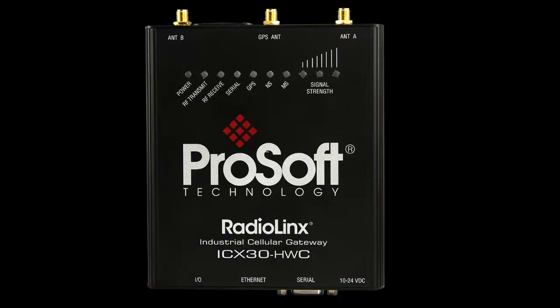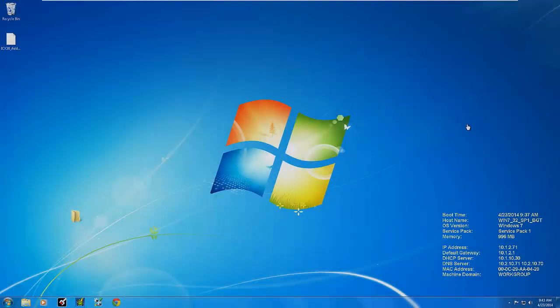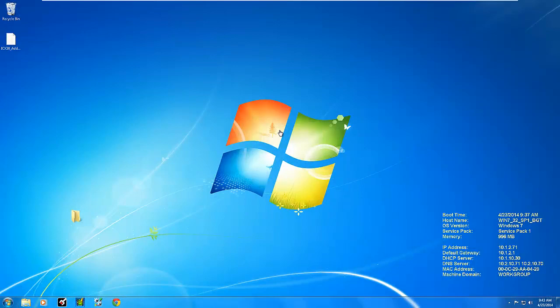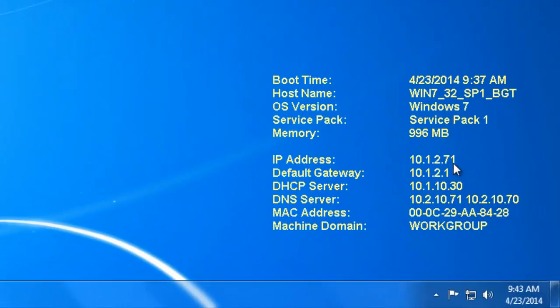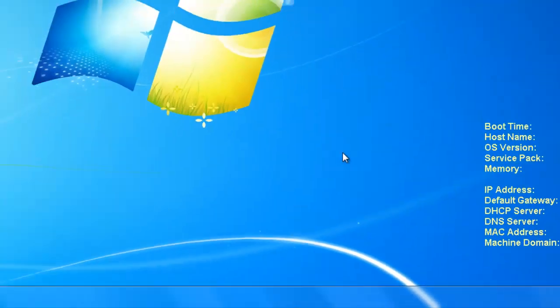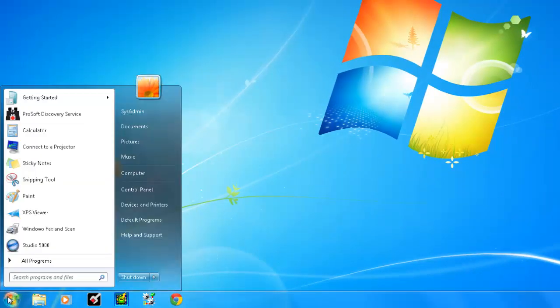When you receive your module it is set to a default IP address of 192.168.0.250. In order to configure this radio we need to have access to that web page. Instead of changing the IP address of your PC we will change the IP address of the cell modem. To do this we need to launch the ProSoft Discovery Service.